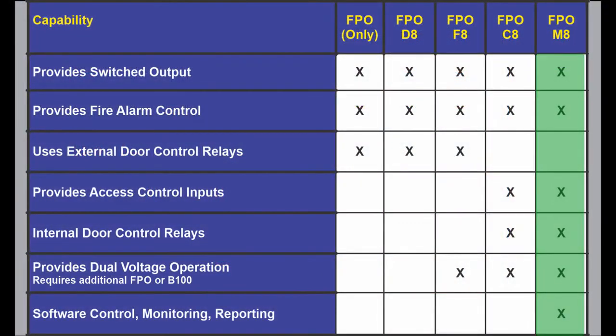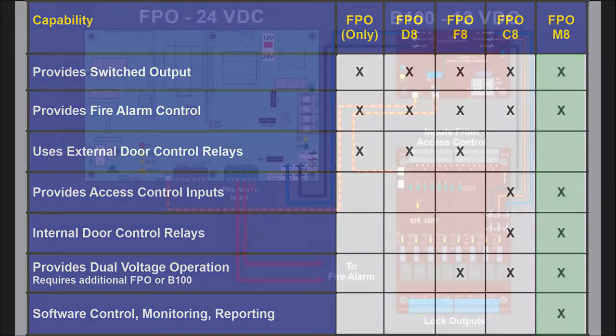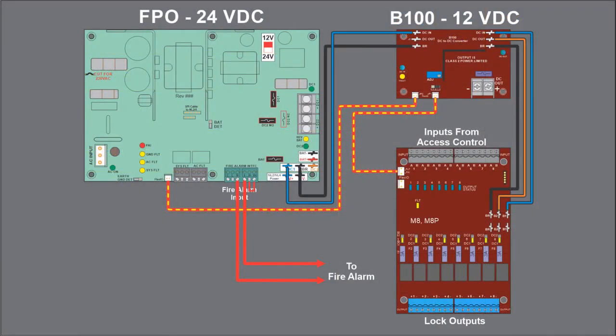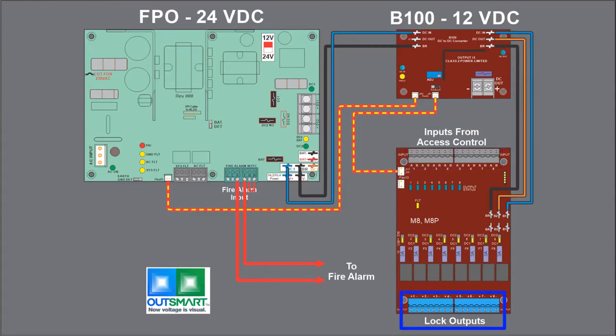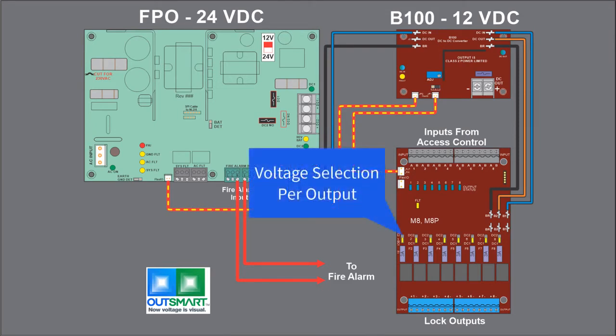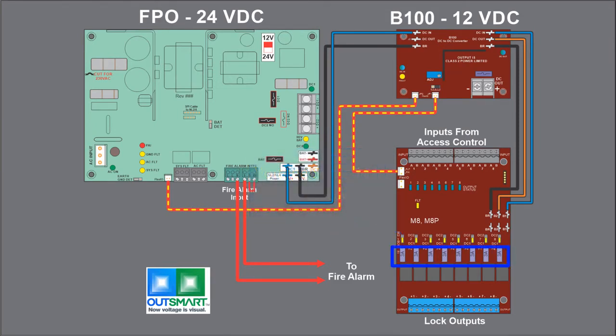The last combination is the FPO M8, which provides all the access control features of the C8, however with some major enhancements. A full-featured lock control board, the M8 has eight inputs to interface to an access system. It's capable of accepting a normally open, normally closed, or a voltage trigger. It has eight outputs to control fail-safe or fail-secure locks, fire alarm interface by output, the ability to work with two voltage sources, and individual fusing or PTC protection for each output.